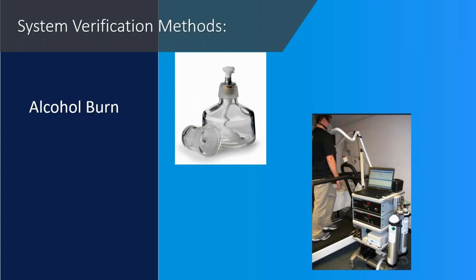For system verification, an alcohol burn produces O2, CO2, and water vapor as byproducts of combustion, and the concentration of each can be calculated using stoichiometric equations. VO2 and VCO2 values from an alcohol burn are typical of resting levels, so it is not practical for exercise testing. Alcohol burns typically provide good accuracy and repeatability for verifying RER; however, VO2 and VCO2 have limited accuracy and repeatability. This method is very low cost and easy to perform.